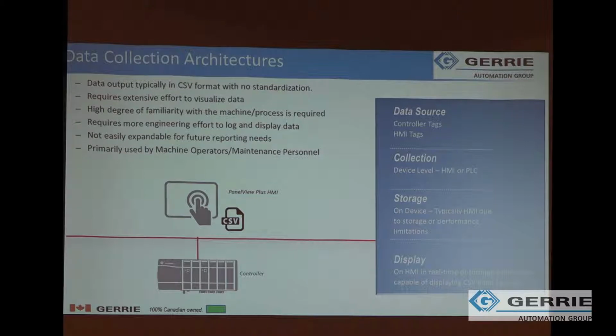So what a lot of people do is pull data from controller tags or HMI tags and typically store it in the panel view or HMI. HMIs are capable of storing data in data logs, in CSV files, saved on the hardware itself or onto server-based storage, but it will be formatted in a CSV. You're not going to see a panel view put out a beautiful report you can pass on to the higher-ups of the company.